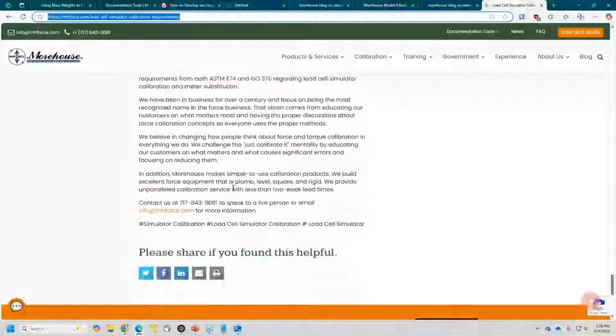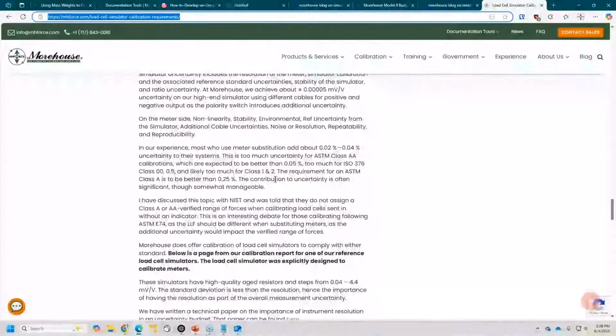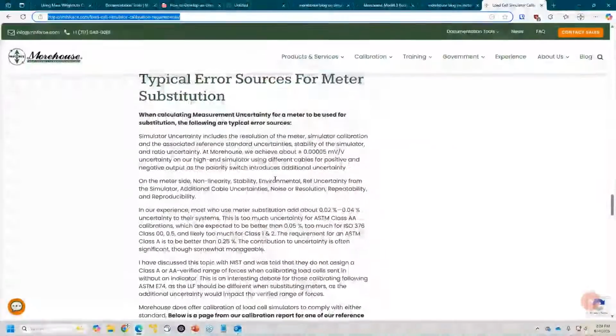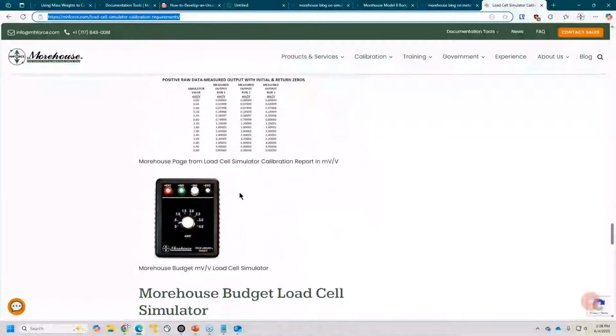But ASTM has specific guidance regarding simulator calibration and what you need to do, and why this wouldn't work for ASTM is because if you had a 2 millivolt, 1,000-pound cell, half a millivolt is 250 pounds, and most people want to use it below that. So going down to that 0.2 value, at least 0.2 gets you 10%, 0.02 gets you 1%. So that's tricky.